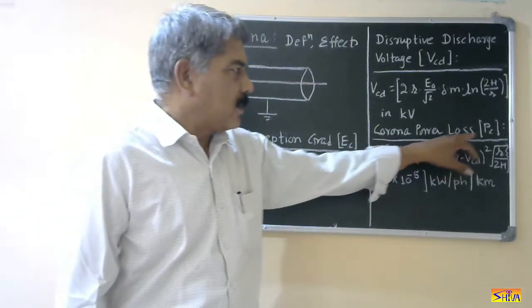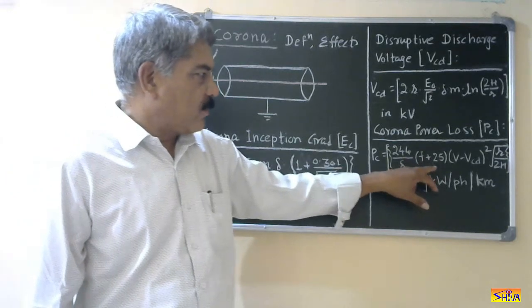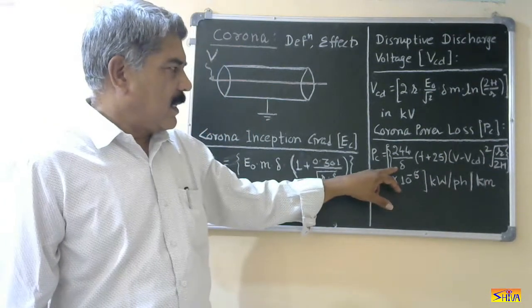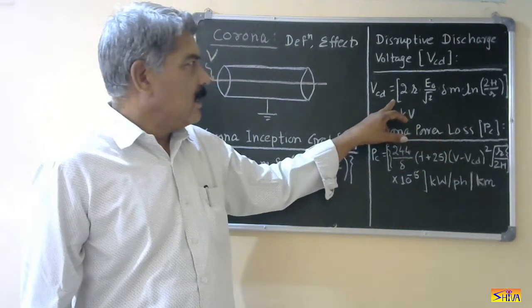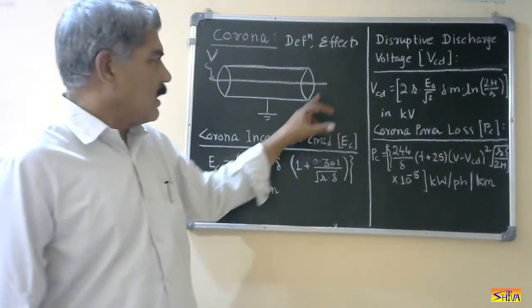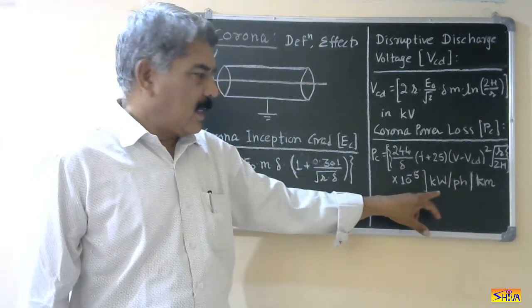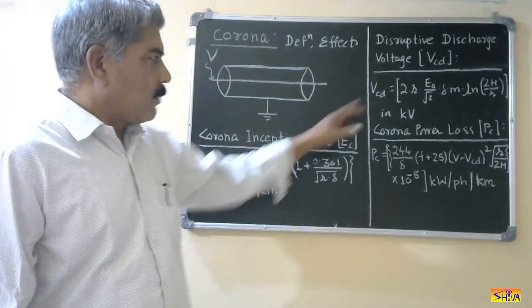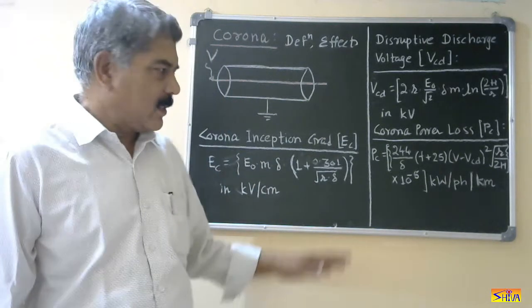The third term is corona power loss, denoted by P_C. The formula is: P_C = (244 / δ) · (f + 25) · (V − V_CD)² · √(r / (2h)) × 10⁻⁵. Here, δ is the air density correction factor, f is the frequency of the supply, V_CD is the critical disruptive discharge voltage, V is the applied voltage, r is the radius, and h is the height of the conductor from the ground. This formula gives the result in kW per phase per kilometer. All three of these formulas — corona inception gradient, disruptive discharge voltage, and corona power loss — are empirical formulas; they are not derivation-based but are statistically determined.